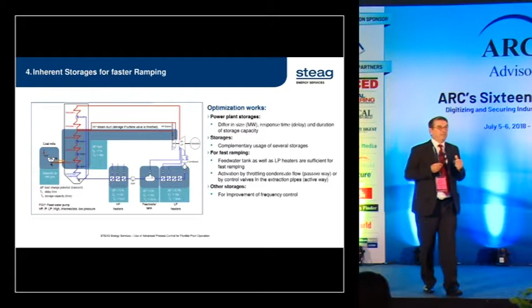When we talk about the reduction of minimum load, we should analyze subordinate controls like live steam temperature control, fuel control, feed water control. We have to make the individual analysis, adaptation, and optimization of each control to the demand, and make a recommendation, for instance, for the exchange of the sensors. In the German power plants, we have flame detectors. For every burner, we have individual flame detectors. In some Indian power plants, we have so-called zonal detectors.